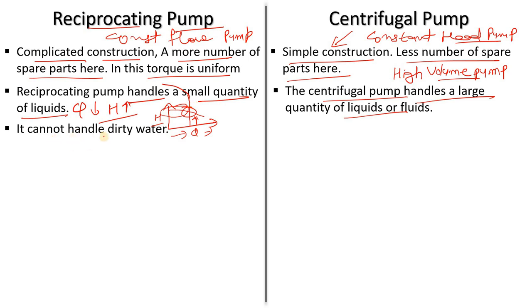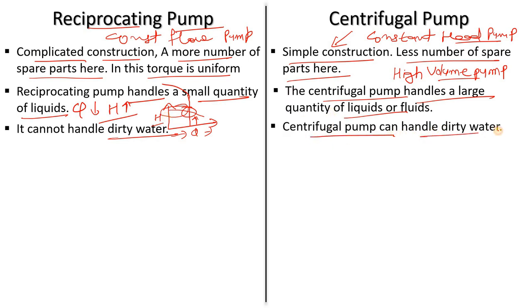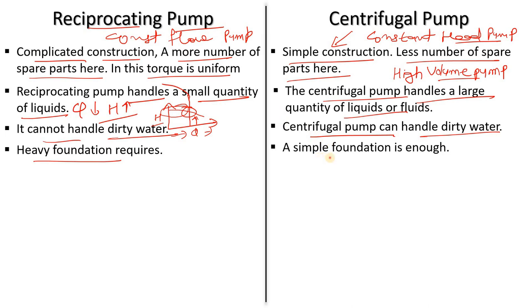A reciprocating pump cannot handle dirty water, while a centrifugal pump can handle dirty water — you can use a strainer at the suction side. Reciprocating pumps also require a heavy foundation due to more noise and vibration, while centrifugal pumps have a simple, lighter foundation.